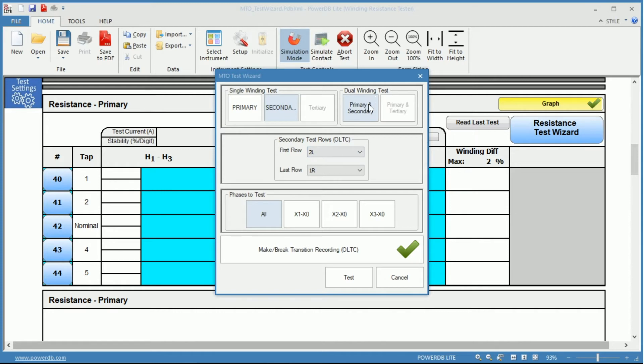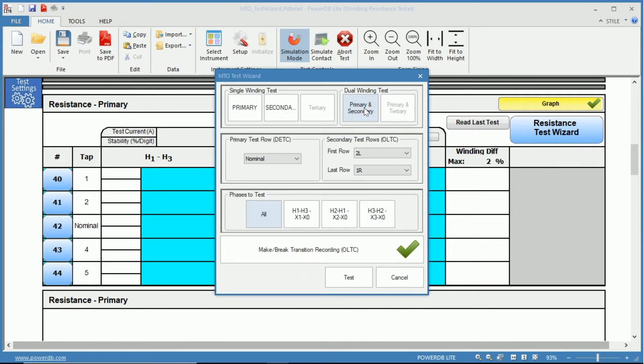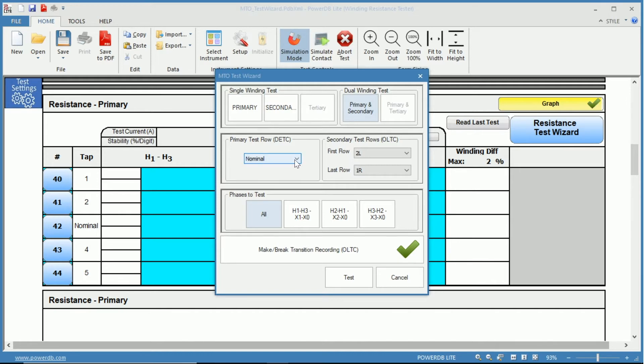On the top right hand corner, we have our dual winding tests. You can see that you can choose primary and secondary, and if you had a tertiary, you could choose primary and tertiary. This tests both windings at the same time, so you can select which tap you are on your de-energized tap changer.